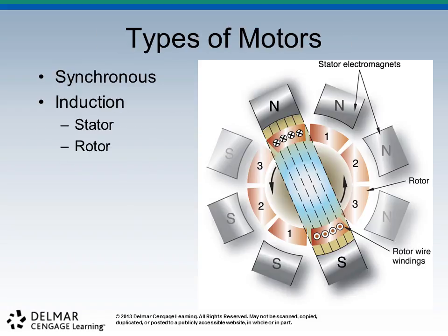Okay, because I've got an X-ray tube that we'll pull out and we'll pay attention to and we'll watch here. So I used the term rotor already, and if you see here on the illustration, the rotor is the interior part that's going to spin. And when we watch our X-ray tube turn, or when you're out in the lab and you depress the prep button on the equipment, what you hear is a whirring sound, and that's this rotor spinning in here.